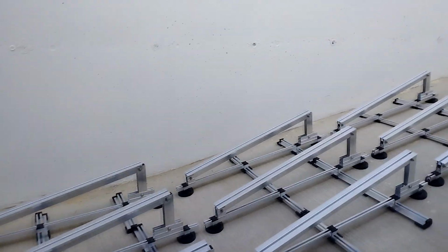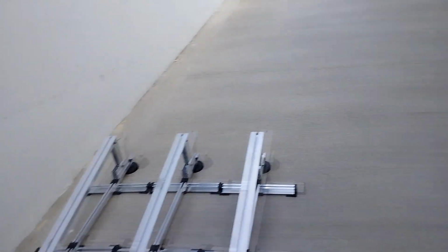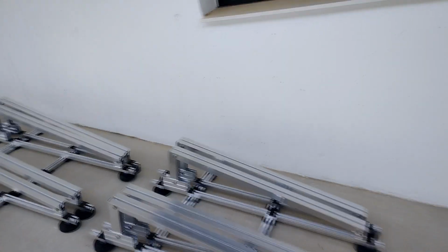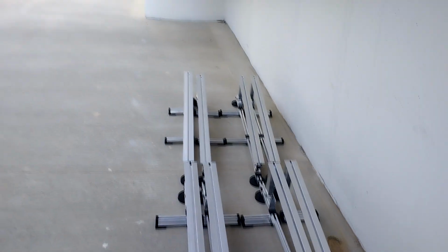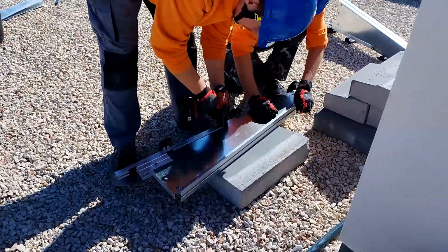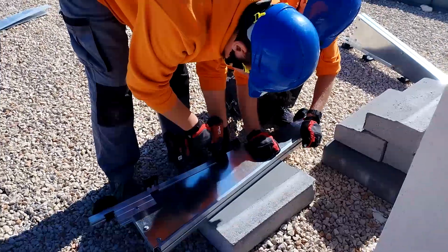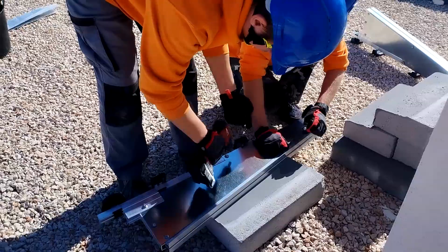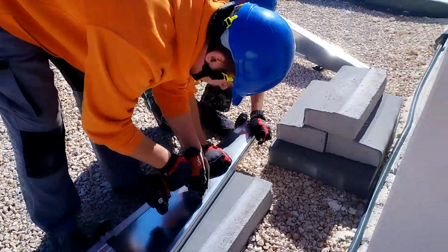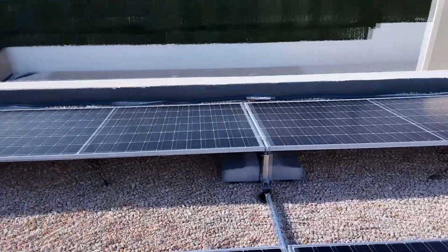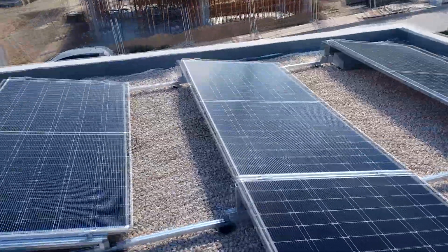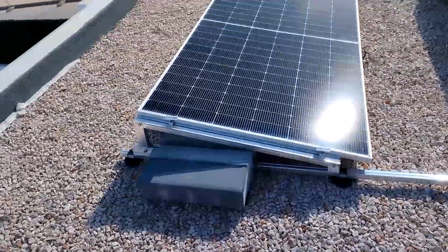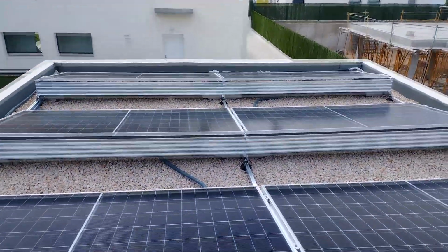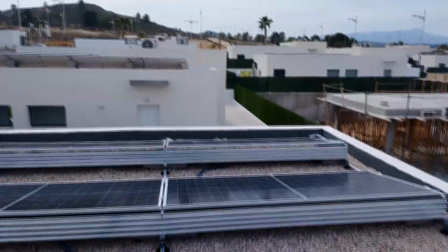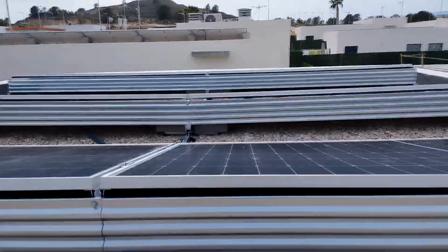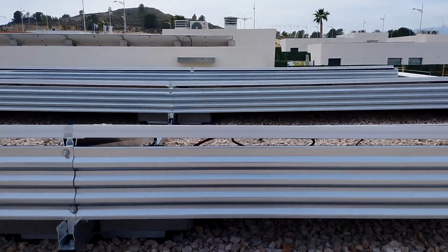1. They are intended specifically for solar panels. We never use generic metal profiles. 2. They are certified for solar installations. 3. They are built for long-term durability. 4. Their design and installation quality ensure proper wind resistance. You can see special concrete ballast blocks used on this flat roof installation. They help the structure withstand strong winds. We also use wind deflectors to reduce wind loading on the panels. Of course, pitched roofs require different mounting systems and technologies.